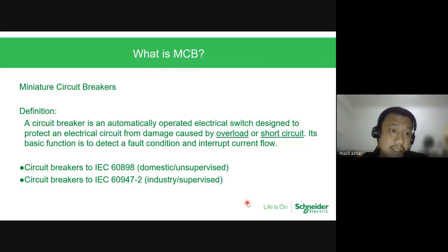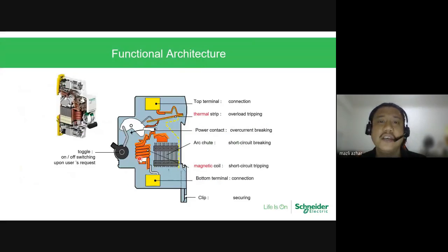What is an MCB? It's a miniature circuit breaker, as I mentioned earlier. It's a breaker that opens when there is an overload or short circuit, where its basic function is to detect and interrupt the current flow. In a nutshell, it provides safety. So two standards, as I mentioned before. Now the functional architecture: if you buy any breaker, or open one of the breakers in your house, but make sure the power is off, you will see each breaker has the same design components, which are the top terminal and bottom terminal for incoming and outgoing, meaning the power goes in and goes out to the load. You will have a thermal strip for overload tripping. So we go in depth on what thermal strips are.